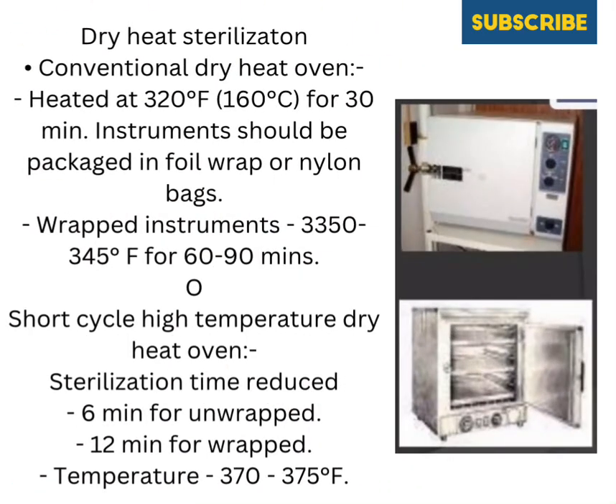Dry heat sterilization. Conventional dry heat oven: heated at 320 degrees F, 160 degrees C, for 30 min. Instruments should be packaged in foil wrap or nylon bags. Wrapped instruments: 345 degrees F for 60-90 mins.